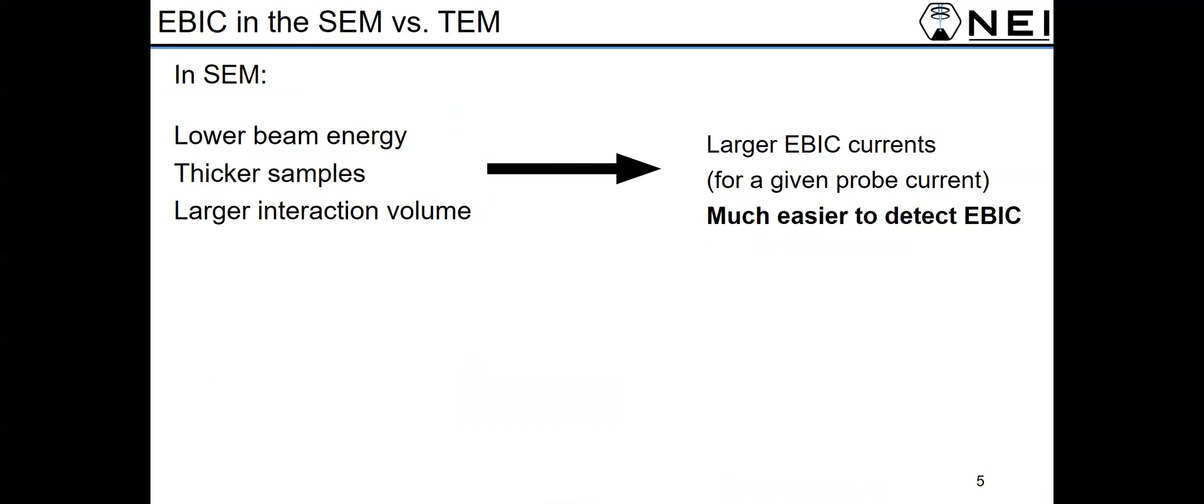Talking generally about measuring EBIC in the SEM, regardless of what type of contrast you're measuring and what EBIC mode you're looking for. In the SEM, you generally have a lower beam energy, thicker samples, and all this makes for a larger interaction volume, which generally means that whatever EBIC signal you're measuring, it's going to be much larger in the SEM. And that means it's typically much easier to detect.